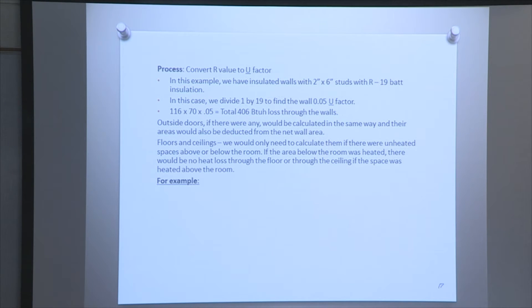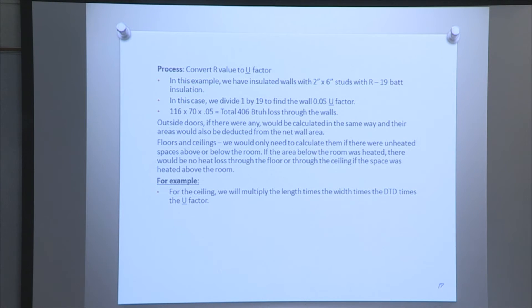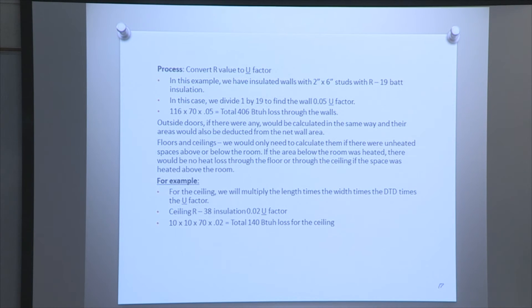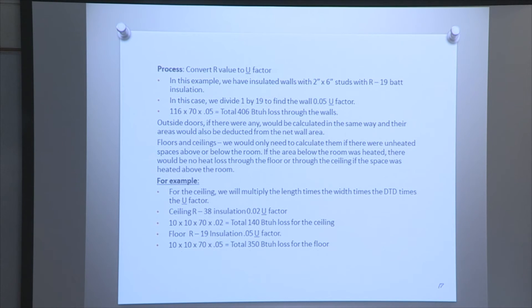Floors and ceilings only need to be calculated if there is unheated space above or below them. If the area below the room is heated, there is no heat loss through the floor; similarly for the ceiling if the space above is heated. For the ceiling: length times width times DTD times U-factor. With R38 ceiling insulation, the U-factor is 0.02: 10 times 10 times 70 times 0.02 equals 140 BTUs of heat loss for the ceiling. For the floor with R19 insulation, U-factor 0.05: 10 times 10 times 70 times 0.05 equals 350 BTUs of heat loss for the floor.